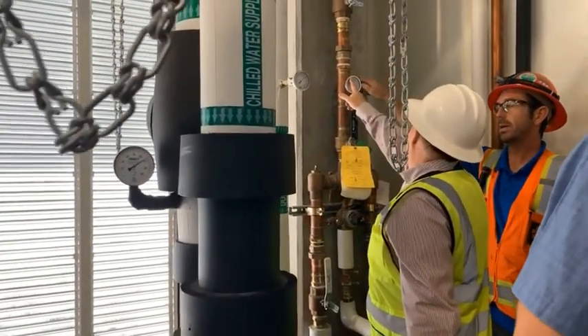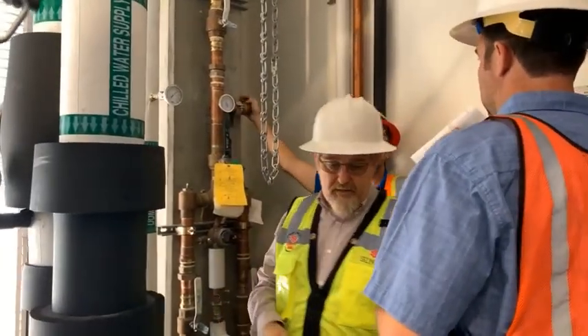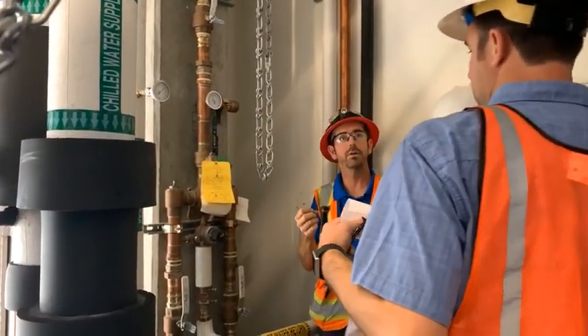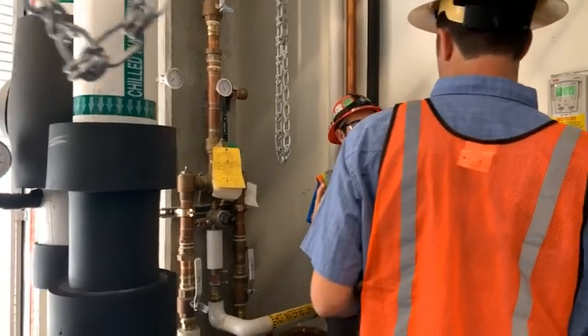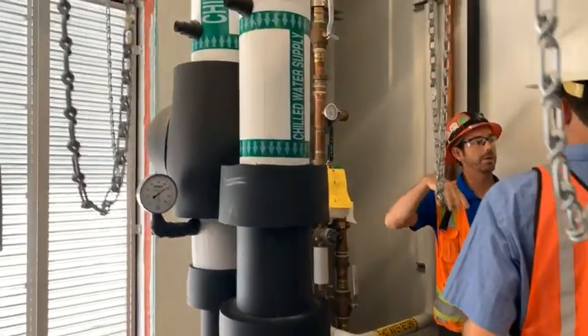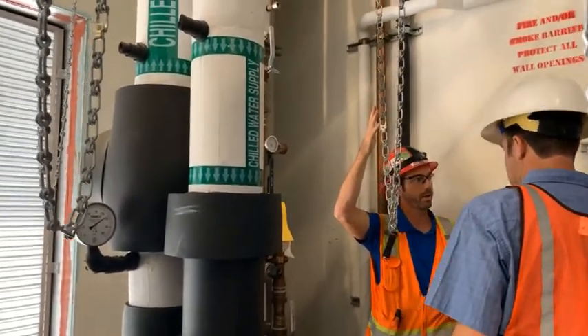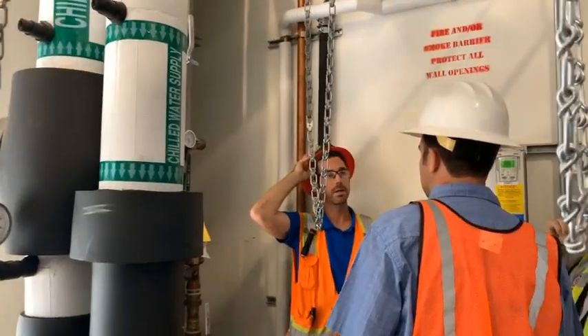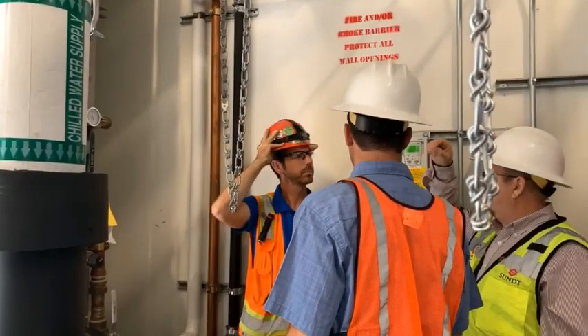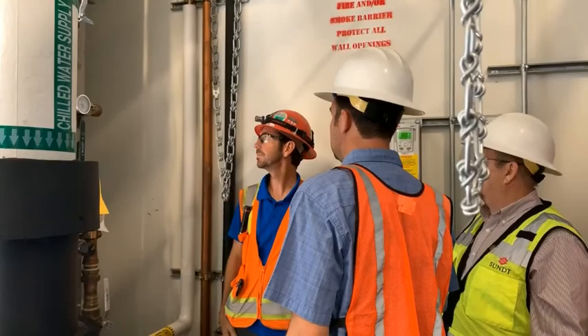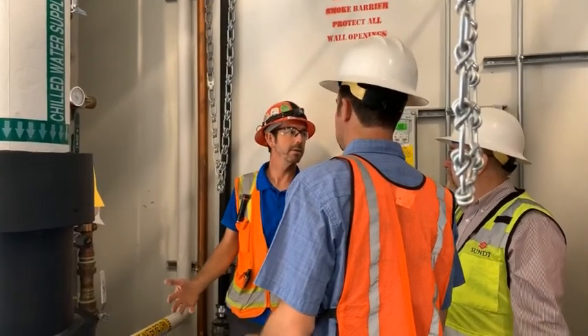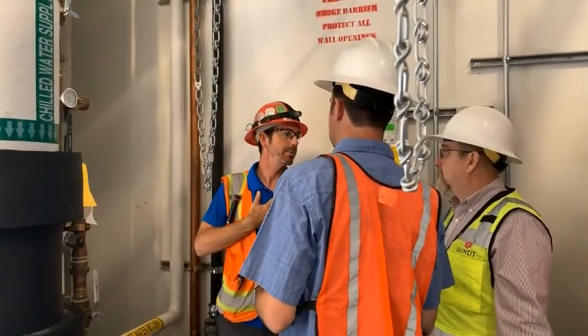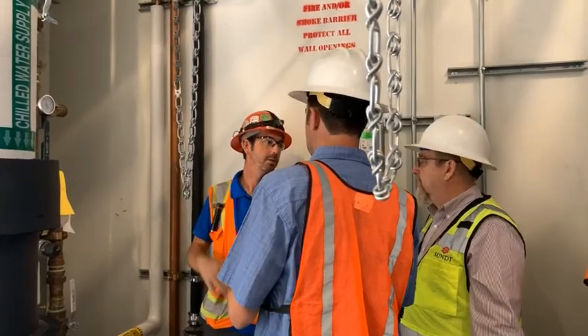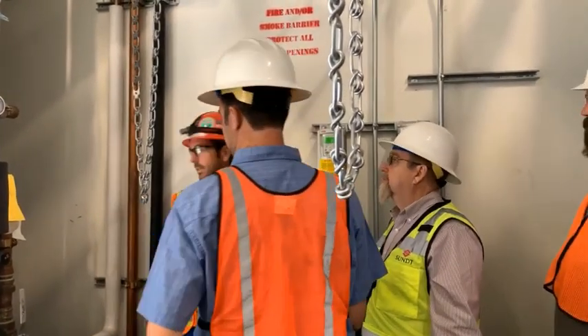So you really gotta get it up to 120. Those valves upstairs will be closed at 115 degrees. So if we're putting it out, we're gonna lose 5 degrees up there. We're already gonna be at 110 and they're not gonna do a good job. So we could use a permanent marker when it's out and just mark the gauge, so you know that. I mean, domestic water, I will never tell anyone to put it over 120. No, I understand. So 120 would be the leaving on domestic water.